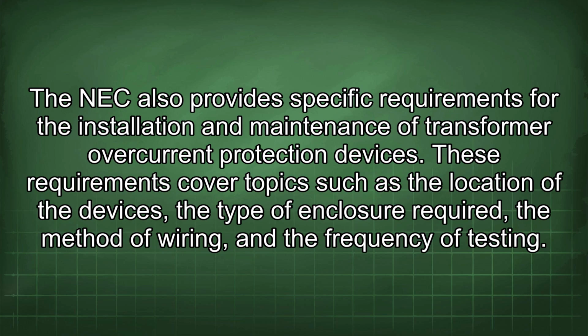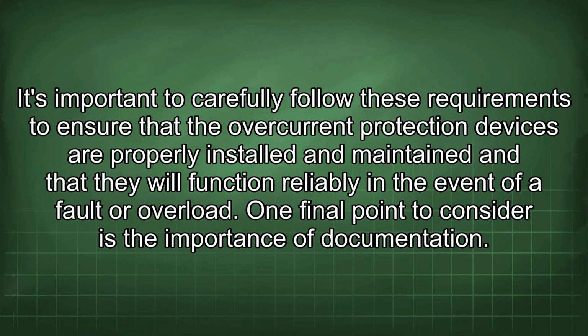The NEC also provides specific requirements for the installation and maintenance of transformer overcurrent protection devices. These requirements cover topics such as the location of the devices, the type of enclosure required, the method of wiring, and the frequency of testing. It's important to carefully follow these requirements to ensure that the overcurrent protection devices are properly installed and maintained and that they will function reliably in the event of a fault or overload.